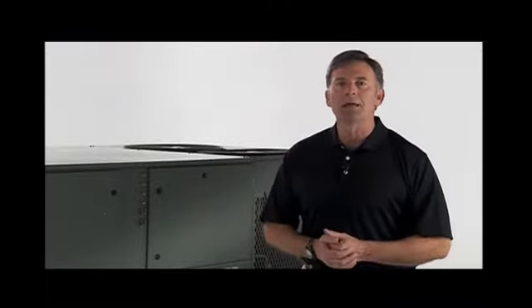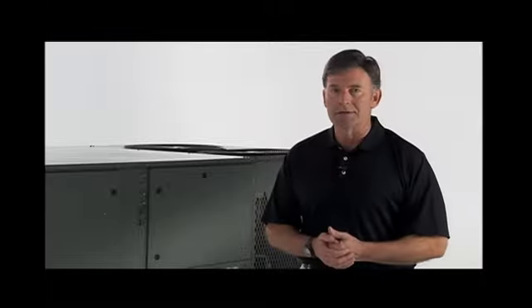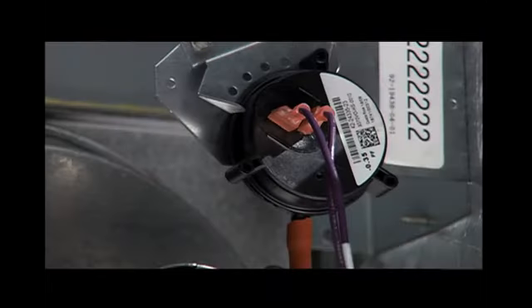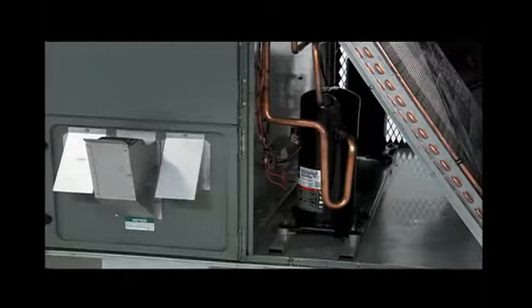The furnace compartment contains the latest furnace technology on the market. The draft inducers draw the flame from exclusive in-shot burners into the aluminized tubular heat exchanger for clean, efficient gas heat. Stainless steel heat exchangers can be factory installed for those applications that have high fresh air requirements or applications in corrosive environments. Each furnace is equipped with a 2-stage gas valve, which provides 2 stages of gas heat input. The first stage operates at 50% of full fire.